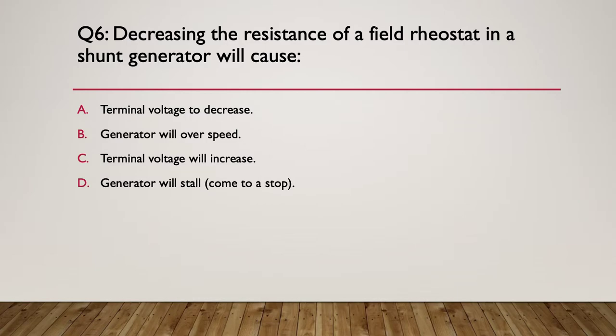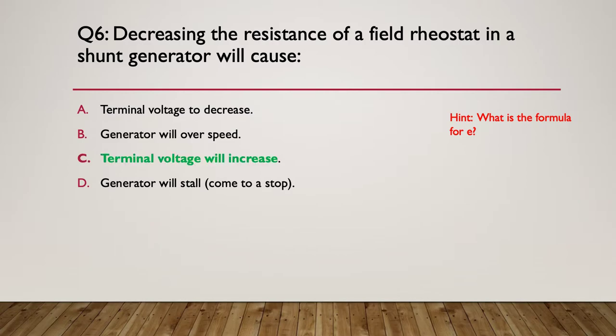Question six: decreasing the resistance of a field rheostat in a shunt generator will cause what? A: terminal voltage to decrease; B: the generator will overspeed; C: terminal voltage will increase; or D: the generator will stall. The answer is C — terminal voltage will increase. Decreasing the resistance of the rheostat means more current flows through the field winding, putting more flux across the generator, which increases the voltage at the terminals.